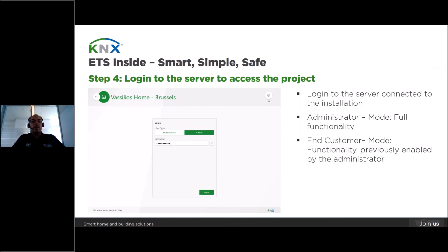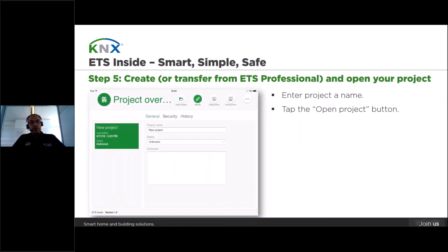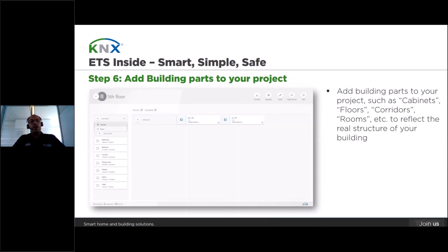Depending on the user type, ETS Inside allows you to log in as follows: administrator with full access to the whole installation, or customer with only access to previously enabled functions by the administrator. Once the correct password is entered, you will see the ETS Inside dashboard. Now you can create a new project, or if you have transferred the project from ETS professional, you can open it by tapping the open button from the main toolbar or select the highlighted project — highlighted in green — which will then open the project and allow you to create the structure of your building. You can create rooms, floors, cabinets, etc., so that the real building structure is reflected in your project.